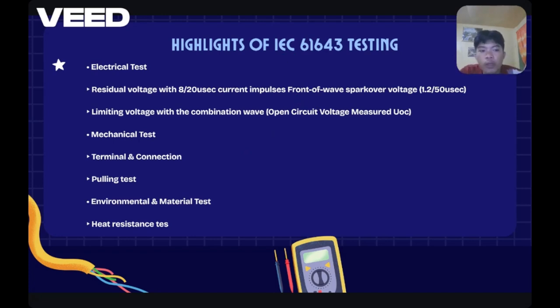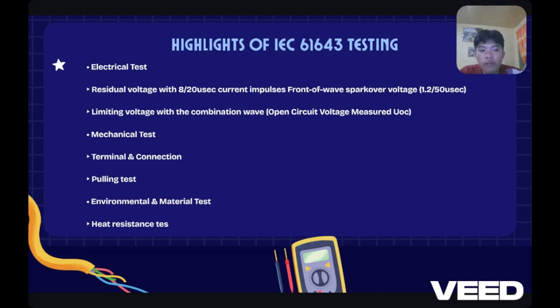So the purpose of this IEC 61643 testing is to confirm the functionality and dependability of surge protection devices or SPD. The device's ability to control surge voltage and manage lightning impulse is tested electrically. Under physical stress, mechanical tests verify the robustness and longevity of terminals and connections. Tests of the device's materials and environment make sure it can endure heat and other challenging circumstances, offering long-term and secure protection.